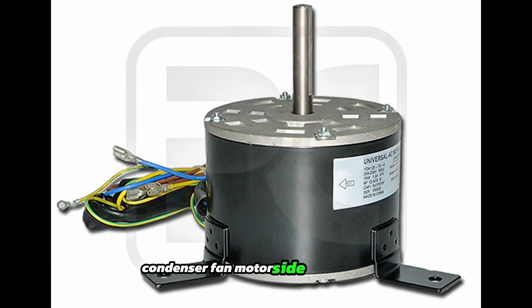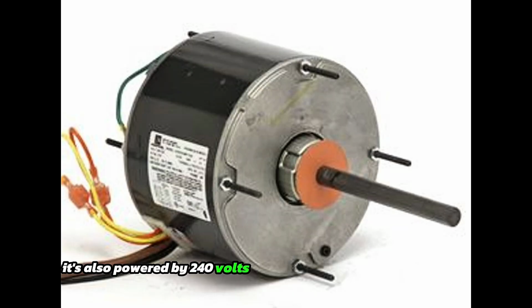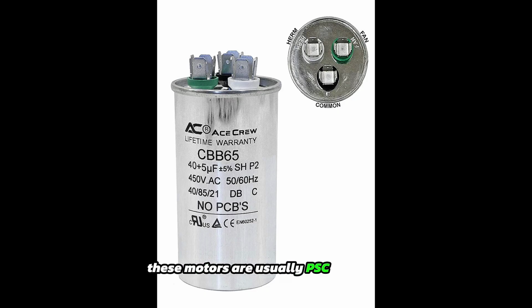Condenser fan motor, outside the house. Outside, in the condenser unit, you'll find the condenser fan motor. Its job is to pull air through the coil to help reject heat from the refrigerant. It's also powered by 240 volts and activated by the contactor when the thermostat calls for cooling. These motors are usually PSC type, meaning they require a run capacitor, typically around 5 or 7.5 microfarads.